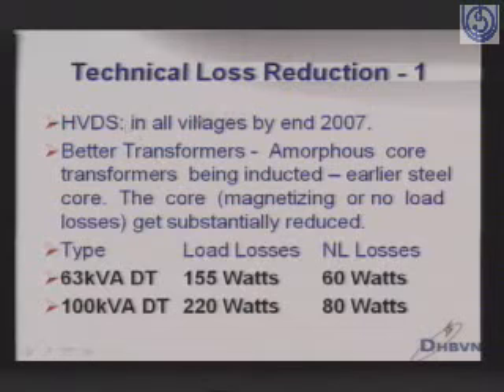One of their programs is high voltage distribution system in all villages by end of 2007, and hopefully by this time they might have achieved it. For better transformers, they would like to go for amorphous core transformers, which have around 70-75% less no-load losses compared to CRGO transformers.